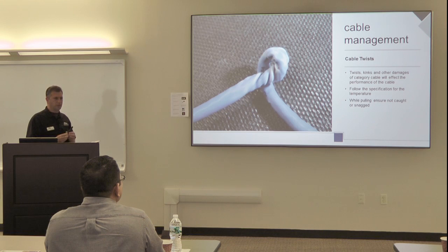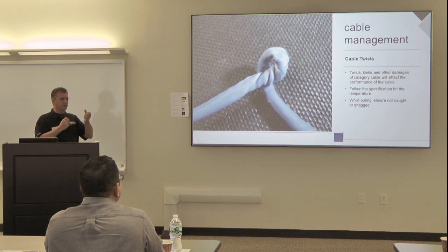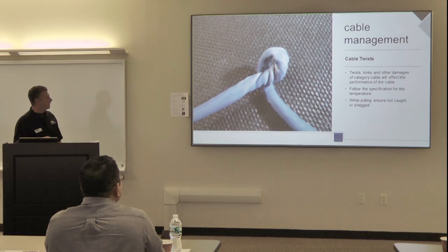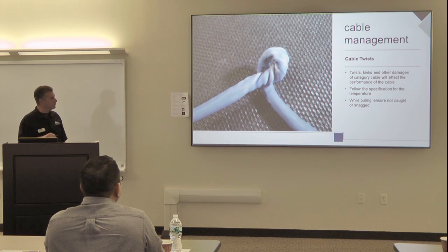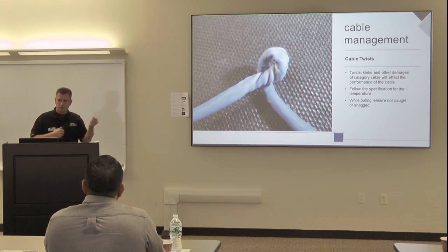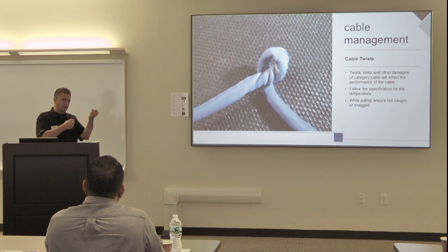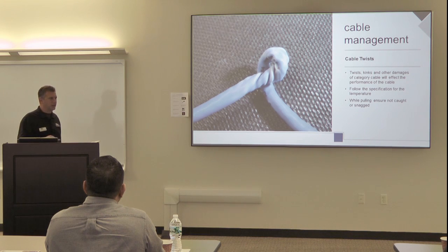I'm sure you've seen this out in the field: you're pulling the cable, and all of a sudden, hey, what happened? That usually happens a lot of times when you're pulling the cable. As you're doing your pre-wire, you may feel a little tug. It could also be related to temperature. A lot of times you may be doing a pre-wire in a building that's not air conditioned or heated, so you could be in a 30-degree room pulling cable. That's going to cause some issues too. That's stated as well, what the temperature range is for the best time to work with the cables.